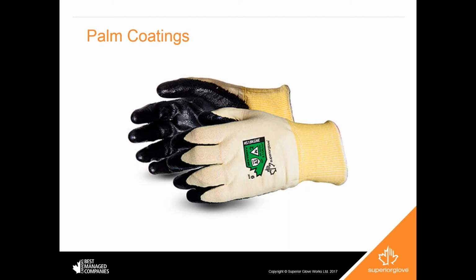The dexterity has been the biggest issue in my dealings with maintenance people, that they put them in the bigger, heavier voltage gloves, and even with a leather protector, they find that they can't do their job. This particular glove now addresses that purely from an arc flash standpoint. Remember, we're not going to be giving you any electrical shock protection with this. The glove is also flame resistant tested according to the ASTM F2675 standard, which, understanding that standard, you test the lowest protection of the glove. In this case, that would be the back of the hand.